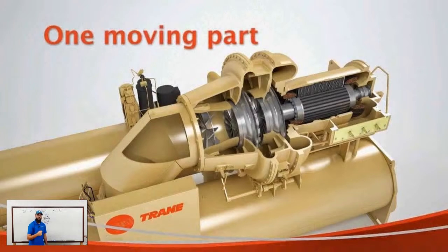This should be a very slow process. These armatures are not going to swing quickly. You're not going to just see it wrench right up. It's going to be slow, small, incremental steps, and it should be. These compressors don't take very kindly to dramatic swings super fast. They'll fight back.